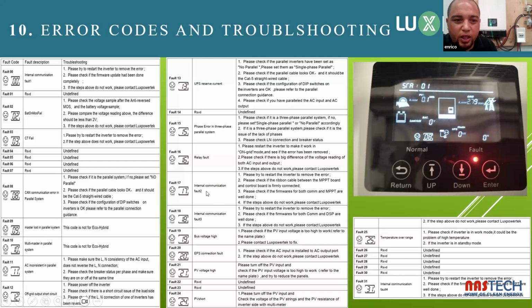Why do I say it's a common fault? It's because, especially with customers using solar panels, there could be a bus voltage over 500 volts. That means that the solar panels, during their conversion to AC, broke a certain component inside on the main board, and this is a fault that requires further inspection from a repair agent. Some of these faults can be cleared with updates.